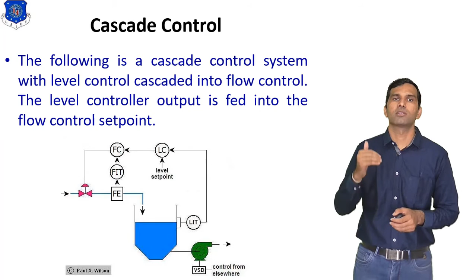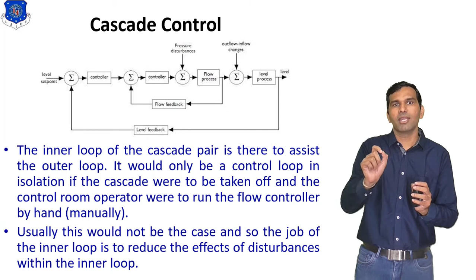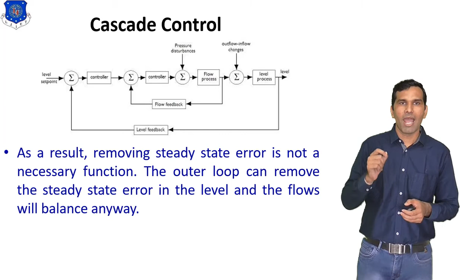Now the inner loop of the cascade pair is there to assist the outer loop. It would only be a control loop in isolation if the cascade were taken off and the operator were to run the flow controller by hand, that means manually. Usually this would not be the case, and so the job of the inner loop is to reduce the effect of disturbances within the inner loop. As a result, removing steady state error is not its necessary function. The outer loop can remove the steady state error in the level and the flow will balance anyway.